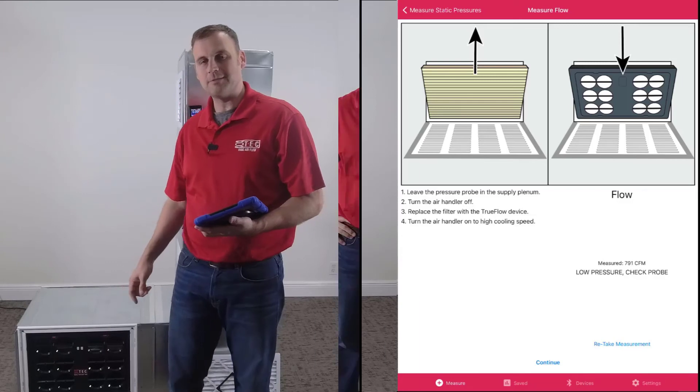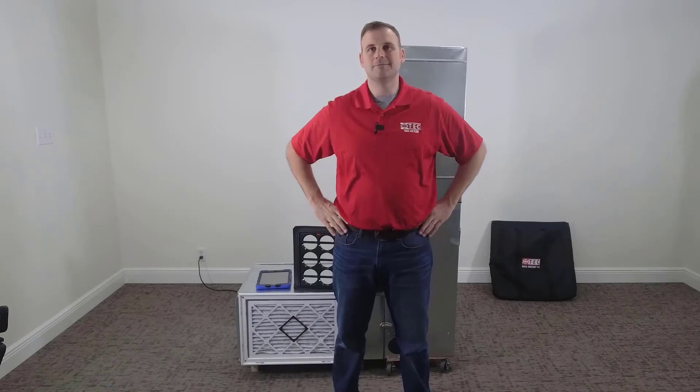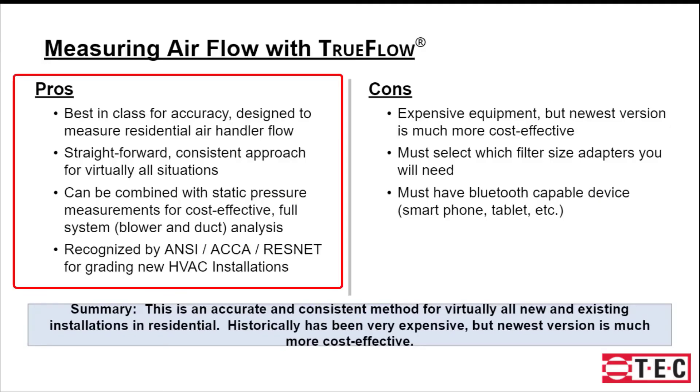Now you've seen a run through, let's discuss pros and cons of this method. Here's the pros: it's the best option as far as accuracy for measuring air handler flow. It has a consistent approach and is straightforward for all situations. It can be combined with static pressure measurements for cost-effective full system analysis. It's also recognized by ANSI, ACCA, and RESNET for grading new installations.